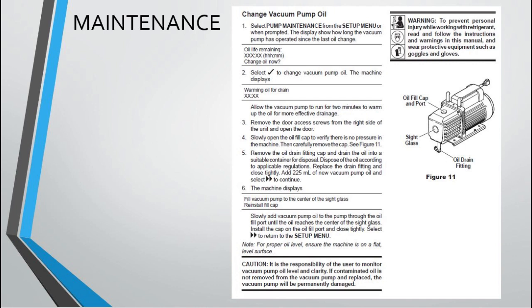Change vacuum pump oil. Select pump maintenance from the setup menu or when prompted. Oil life remaining will display. Change oil now? Select check. Warming oil for drain. Allow the vacuum pump to run for 2 minutes to warm up the oil for more effective drainage. Remove the door access screws from the right side of the unit and open the door.